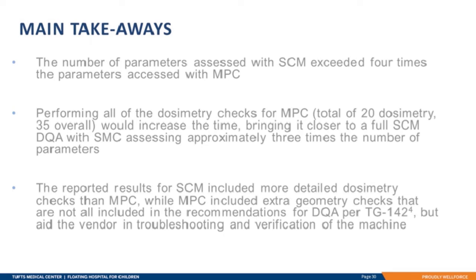We see benefit in performing these tests, as if there is an issue with the Linac, the tolerances are set such that you know immediately that it is out of spec for the vendor and that you have a history of how those tests have been performing for your service engineers. As was seen, running the machine performance check tests in an alternating fashion does not add a significant amount of time to the total daily QA. So for our clinic, the benefit outweighs the cost.